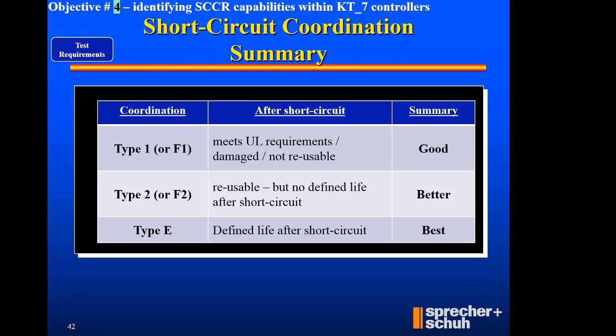So let's put this together again. What we just said was, from a short circuit summary, what is type 1 versus type 2. Type 1 meets UL requirement, says, hey, it can be damaged, but not reusable. So, okay, that's good because it gave me the protection and didn't hurt nobody and was safe. Moving a step further is type 2 that says, hey, I'm going to be reusable after that short circuit, but there's no guarantee of how much life you're going to get for that product after the short circuit. So, hey, I can reuse it, so that's better.